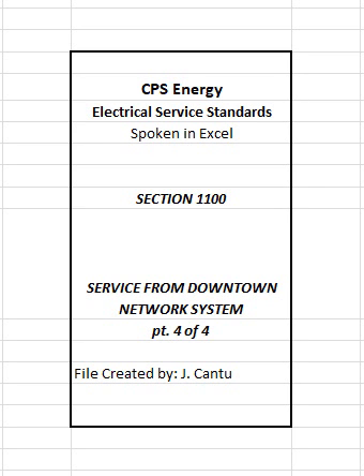1105 Metering. CPS Energy metering equipment shall be located immediately adjacent to customer's service equipment on customer's premises. Where instrument transformer rated metering equipment is required, then CPS Energy will furnish instrument transformers and standard enclosures, which shall be installed by customer. Where customer's service entrance conductors exceed the maximum allowable conductors permitted within CPS Energy furnished metering enclosure, customer shall furnish a pre-approved metering enclosure.